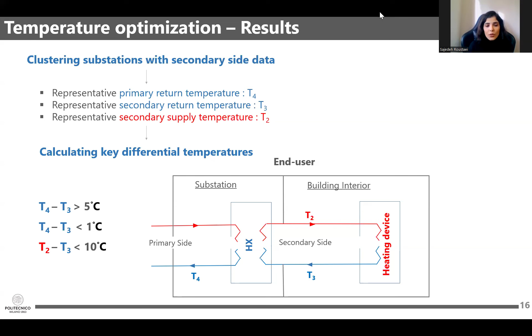Another key differential temperature was related to both sides of the heating device inside the user's building. Because we're dealing with a system mostly consisting of radiators in this network, we considered a threshold of 10, which is a design value for sizing radiators. So if this value was lower than 10, it showed that the inefficiency was coming from the heating device of the user.